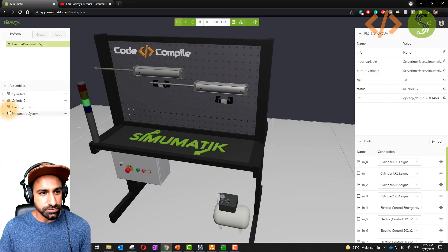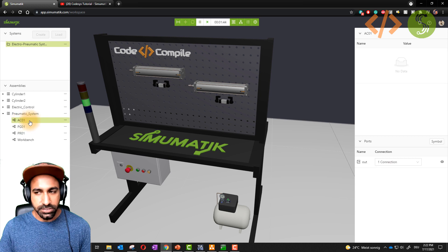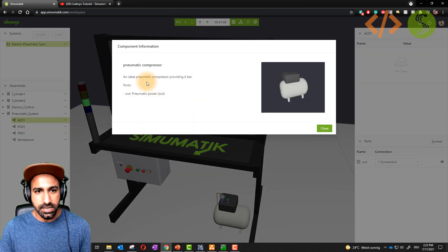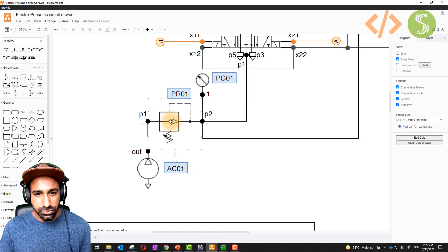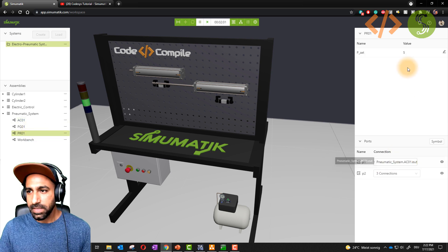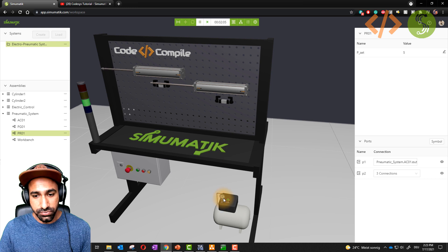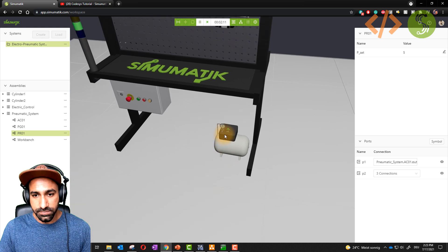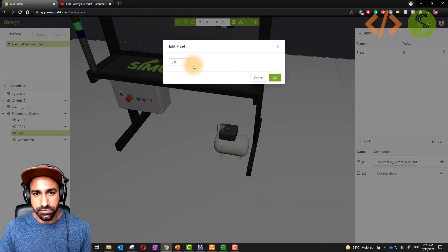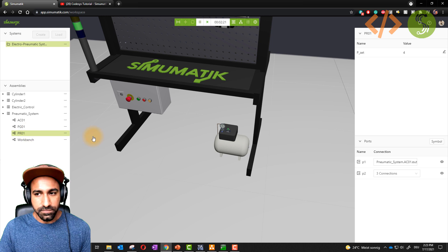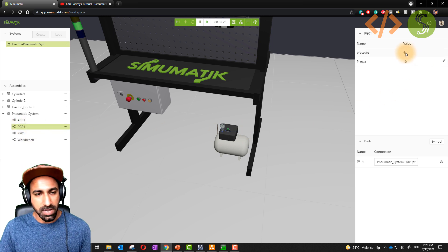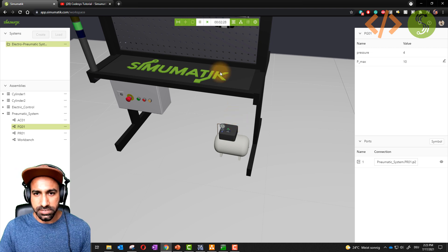If I go to my pneumatic system and select AC01, that's my compressor. Going to its info, I see it's an ideal pneumatic compressor providing six bars. Then this is connected to PR01, the pressure relief valve. On PR01 you can set the pressure — for example, five bar. I can also change that; right now I'll reduce it to four bar. If I click on PG01 you can see the value is four bar. Four bar is also an ideal pressure for small pneumatic applications.